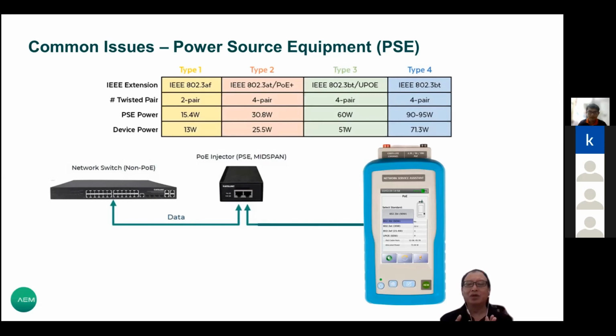If you get less than that, it can be two things. One is your power source equipment does not give you the right power. Second, your cable is no good. Your cable has high losses. So how do you determine that? First, you can plug directly. That means you use a simple short patch cord, plug the tester to the power source, so you can measure your output power. This measurement will determine whether your power source equipment is good or bad. Second, if you plug in a long 90 meter cable to measure the actual power, this one can determine if your cable is good or bad. So you do two steps. That is how you measure the PoE. I hope that answered.